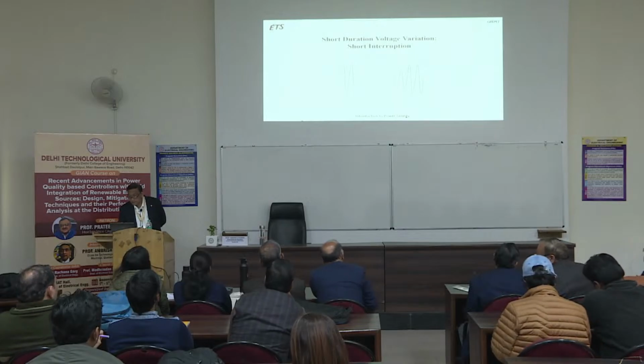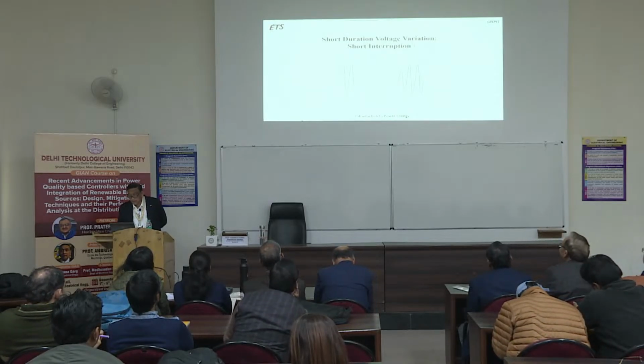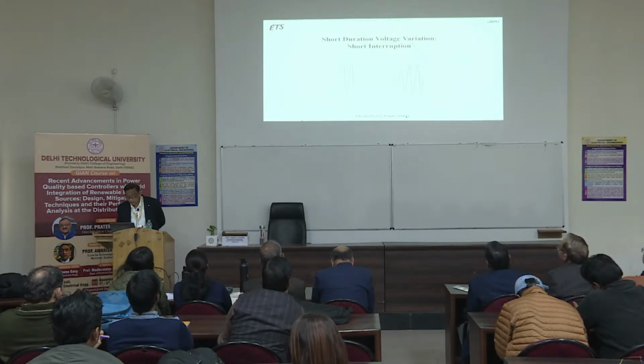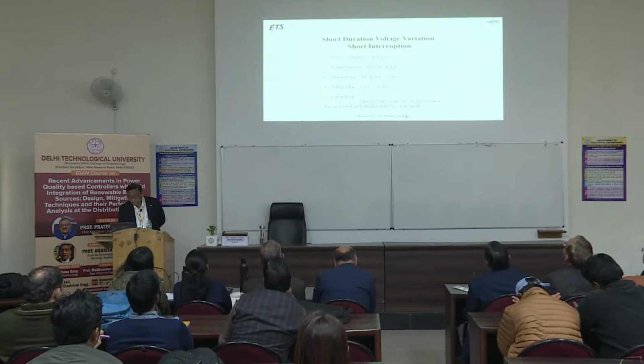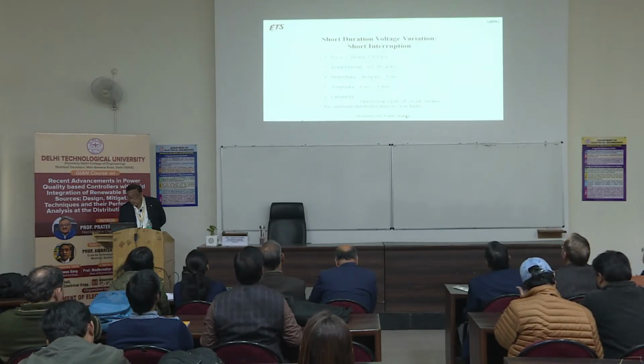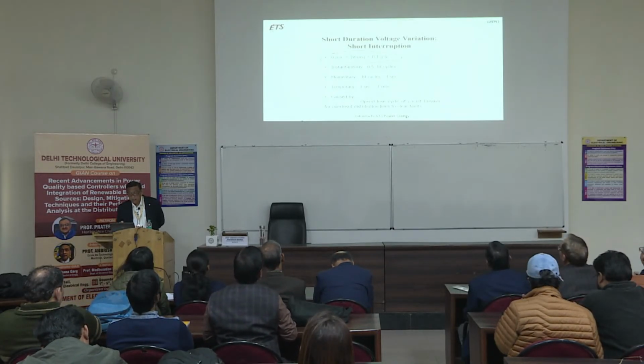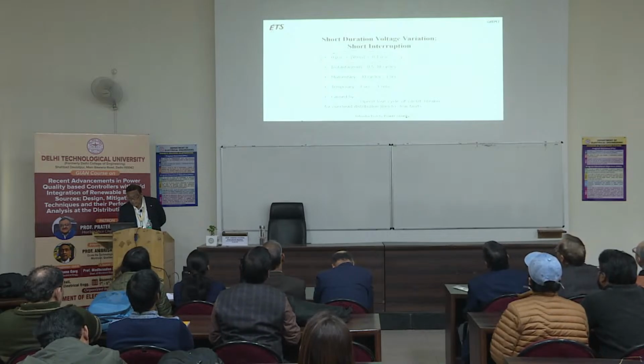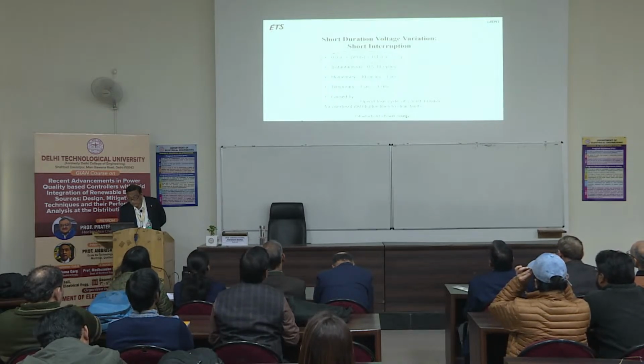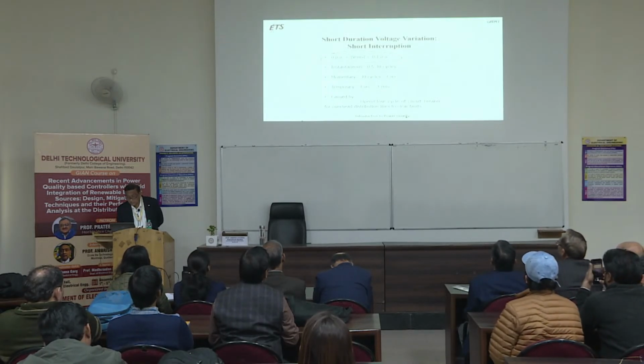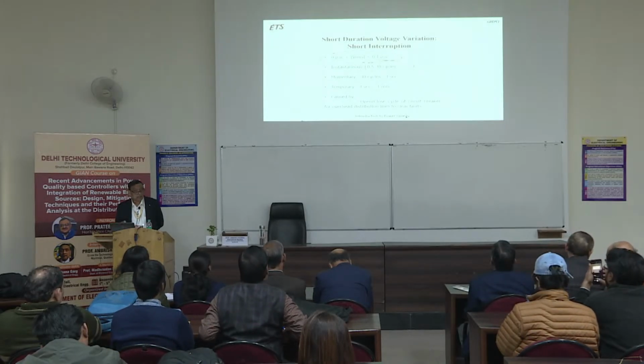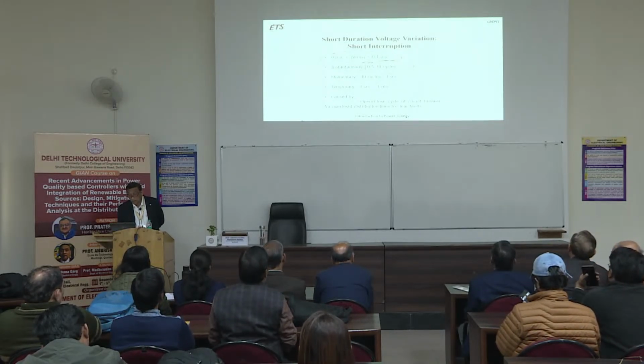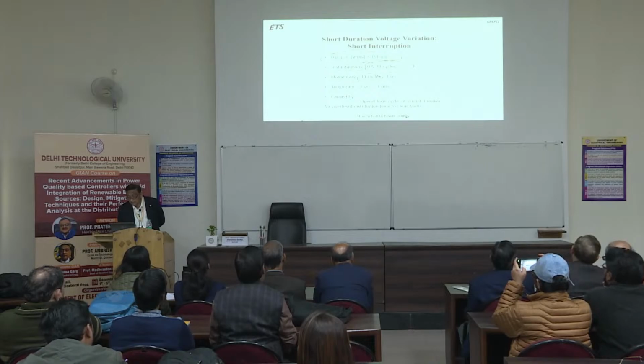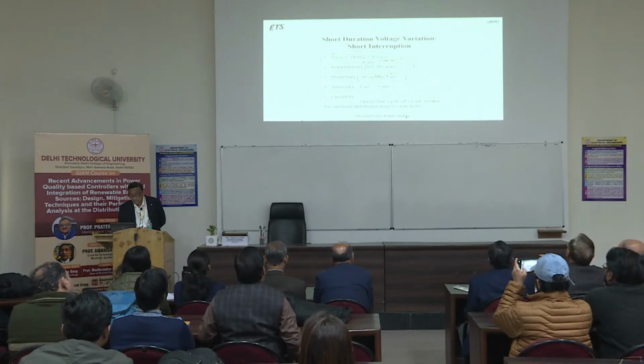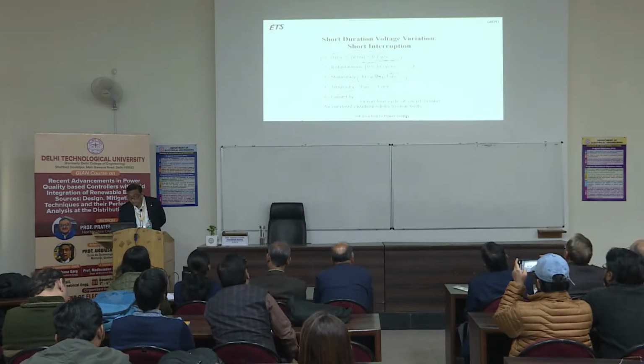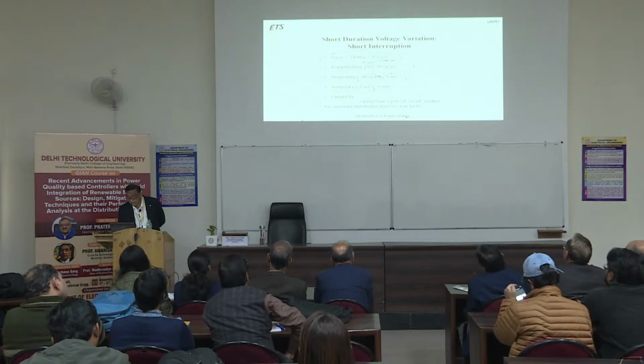Short interruptions: for certain period of time, there is no electricity. This is the short interruption. The voltage is between 0 pu and 0.1 pu. And there are three types: instantaneous, momentary, and temporary. Instantaneous if it is between half cycle and 30 cycles. Momentary if it is between 30 cycles and 3 seconds. And temporary if it is more than 3 seconds and less than 1 minute.